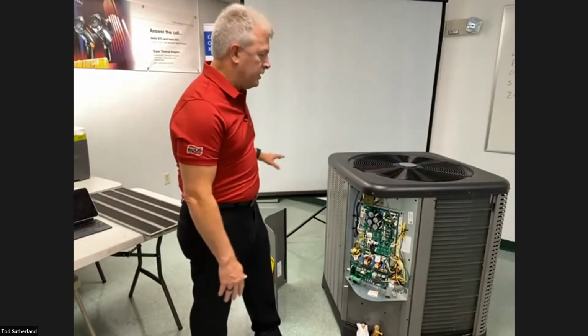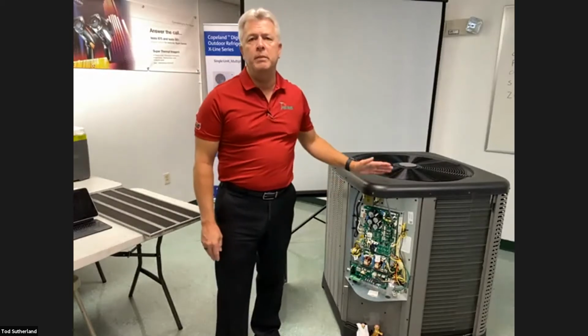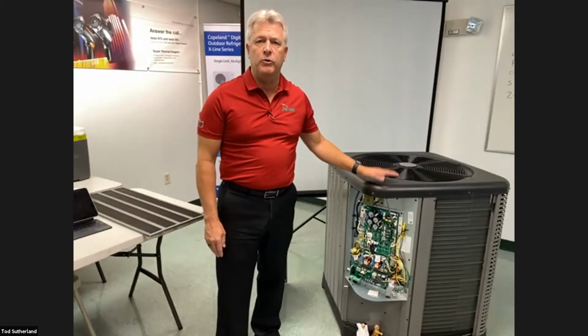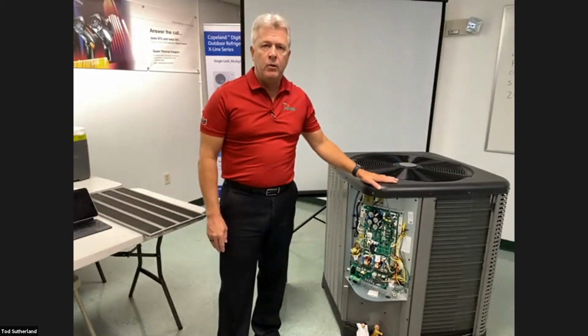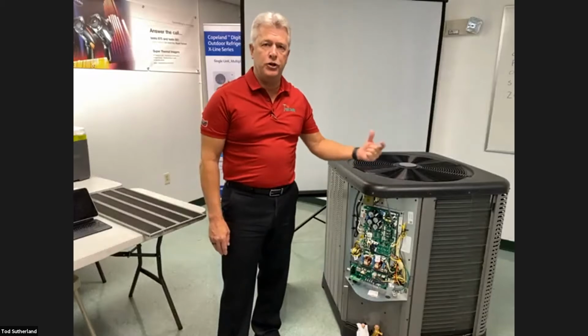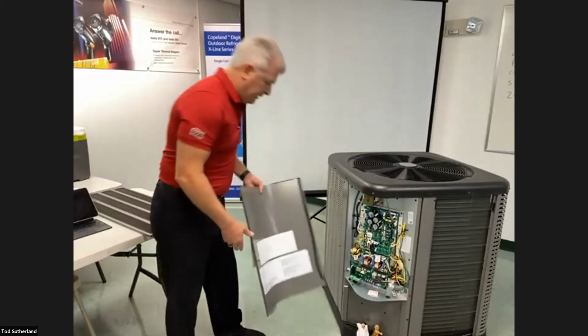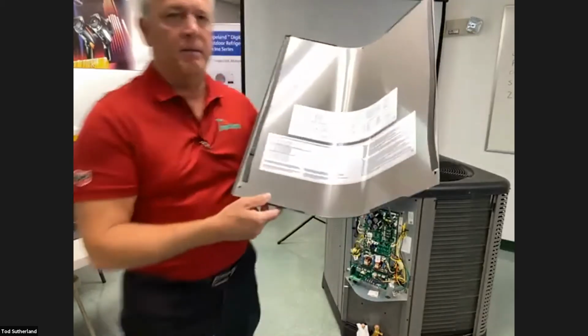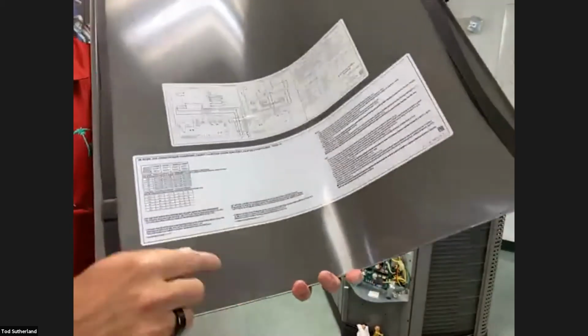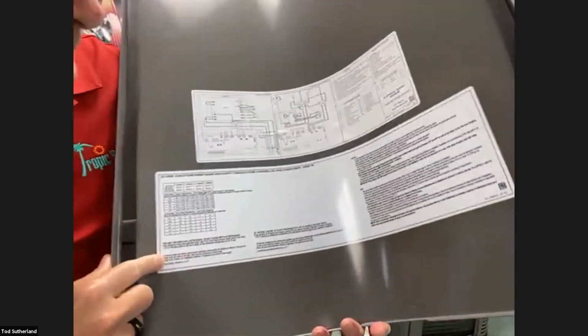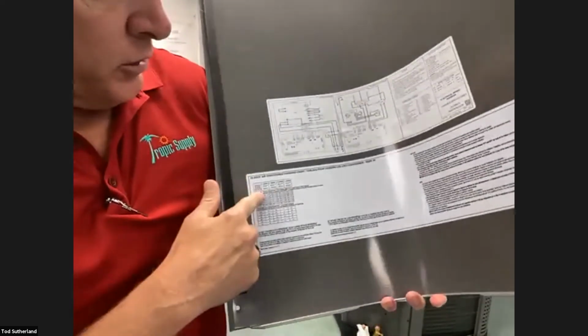When you're adjusting to the gross charge, Ruud wants you to be between 78 and 82 degrees on your indoor ambient. Once you've adjusted that to the gross charge, which is on your chart, I know it's probably very difficult to see. Can you see this here? Probably not. But this is basically your gross charge here.